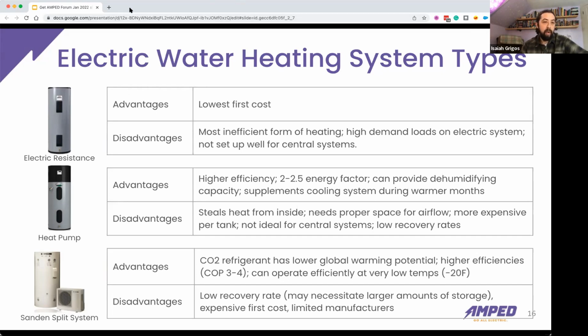We're seeing upgrades to this, such as the integrated heat pump water heater. The next one down is a heat pump water heater, with a condenser unit on top and a storage tank below. This unit pulls heat from the surrounding air and puts it into the water. They're usually very efficient but have some requirements, such as space around them—since it's pulling heat from the air, you can't just stick it in a mechanical closet. You need something like a louvered door so air can circulate from the apartment into that closet, or you can duct it, pulling air from the living room and pushing it out somewhere less noticeable, like underneath the stairs. It can be noisy, and it will blow cold air out of one side, so you have to be aware of both of those things.